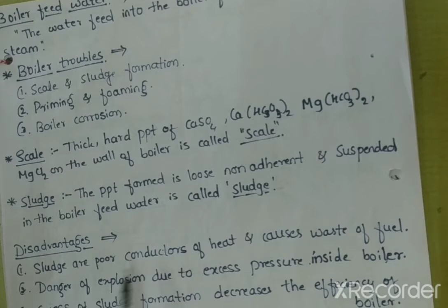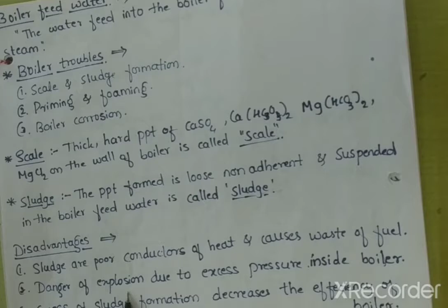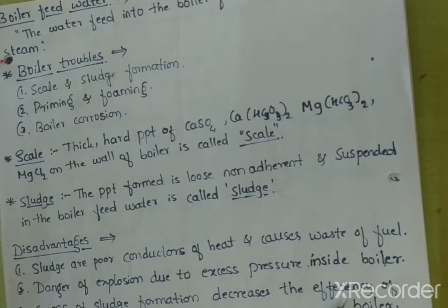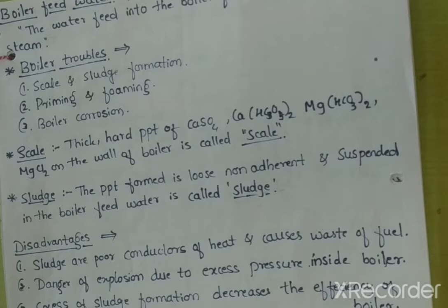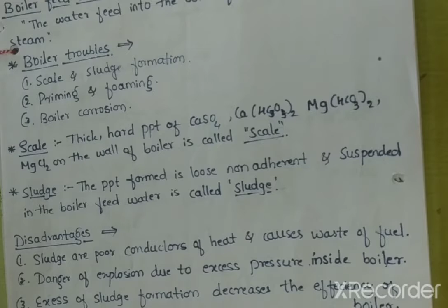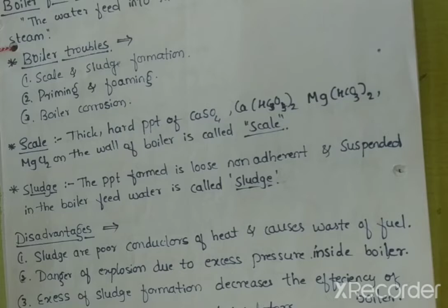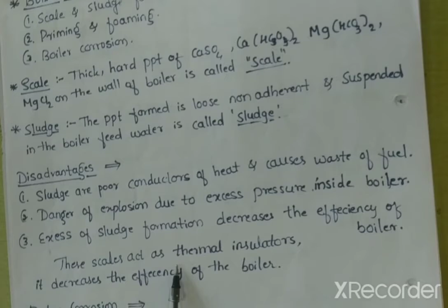The second disadvantage is the danger of explosion due to excess pressure inside the boiler. If the boiler is corroded, or the formation of sludge and scale is more, then it may explode due to the excess pressure. Excess sludge formation also decreases the efficiency of the boiler. Efficiency means that even if you provide more and more fuel, the water will not get heated very soon. These scales act as a thermal insulator, so they do not conduct heat correctly and fast, and this decreases the efficiency of the boiler. So this is all about the disadvantages.